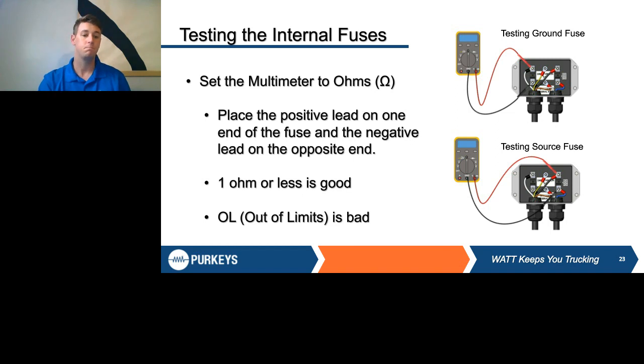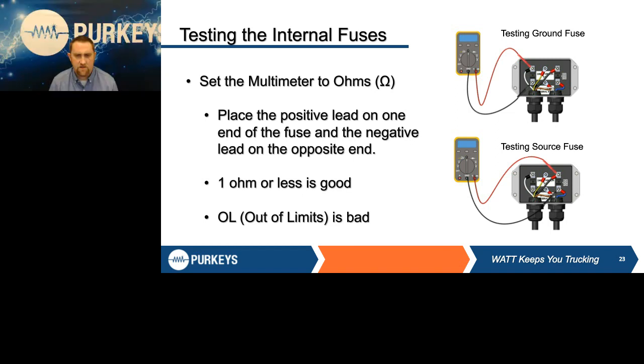Just to add to that, we put this in here because the first thing most of us do when we think it's a blown fuse is take it out and hold it up to the sunlight to see if the element's broken. I've witnessed it firsthand - it may not look broken, but there could be a break in that element you just can't see. So to keep from going down the wrong path on diagnosing, it's best to use the voltmeter and check it the proper way to see if it's blown or not.